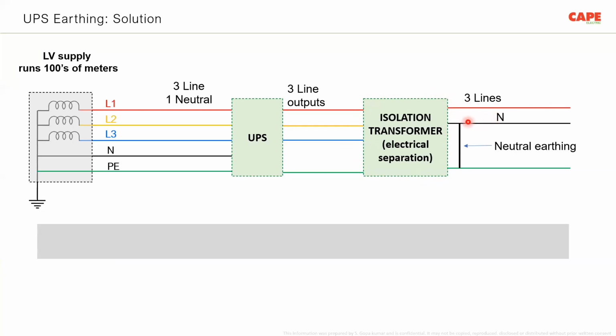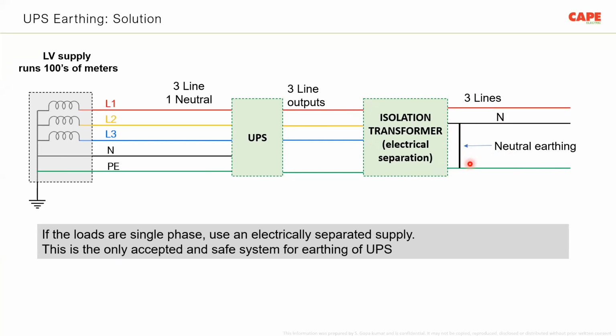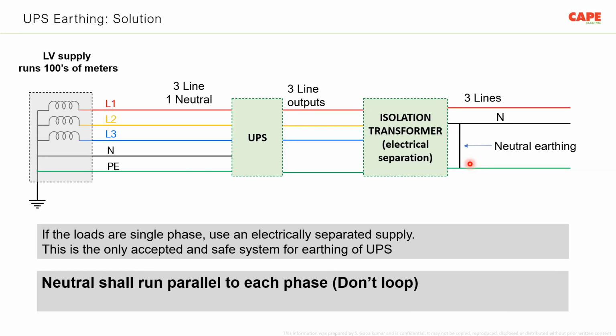Then you have 3-phase, there is a neutral, there is an earth conductor, the PE conductor. The neutral must be connected to the earthing in this fashion. This link is the neutral earthing. This has nothing to do with the earth pit in soil. If the loads are single phase, use an electrically separated supply. This is the only accepted and safe system for earthing of UPS, especially when we use single phase load.